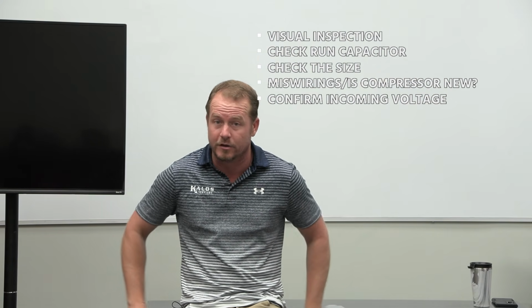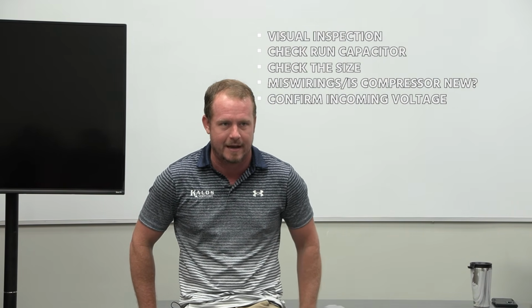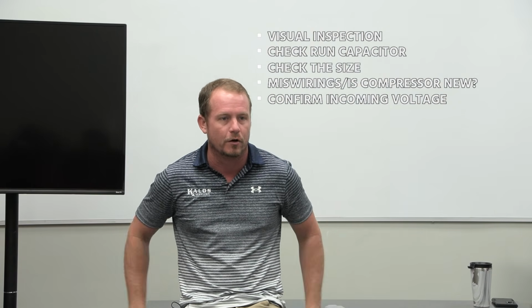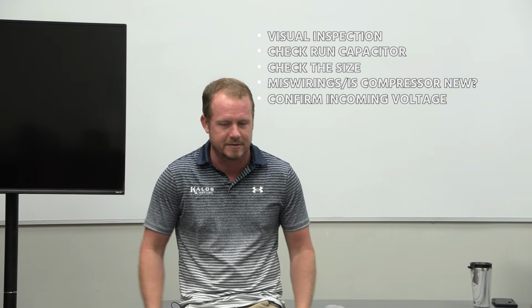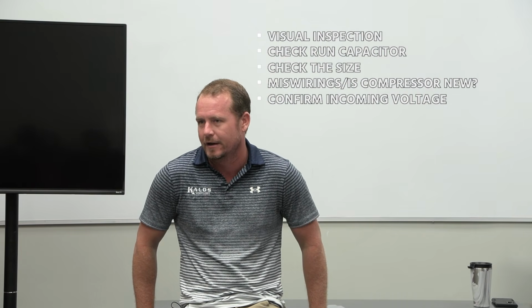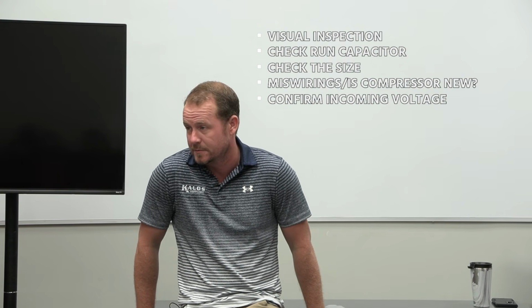Because somebody could have put the wrong compressor in, maybe the wrong voltage, or maybe put a 3-phase compressor in for single phase. All kinds of weird stuff like that can happen, and you want to have your mind open to all those possibilities, just to make sure that it's all correct. Now again, you walk up to the system, it's clearly the same compressor that's been in there the whole time. You can look at the braze connections and tell. Then at that point, you're not going to worry as much about that, although anything is possible, of course.